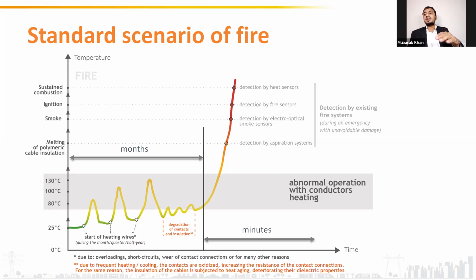After that, maybe in another overload scenario, again the temperature of the joint will increase. When the load clears, the temperature will come down again to a higher value. This cycle will repeat multiple times. At one point of time, the contacts will get degraded so much that the temperature of the joint will start to increase rapidly.